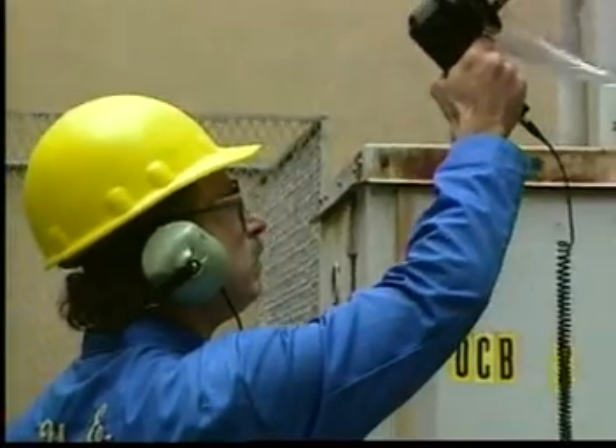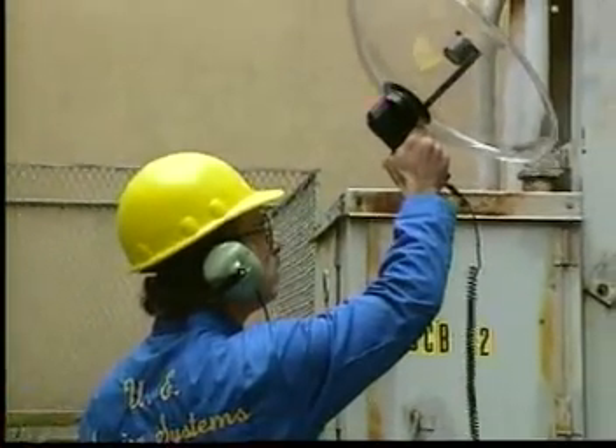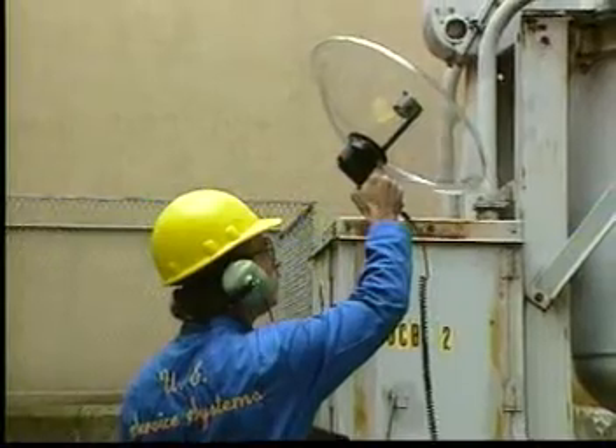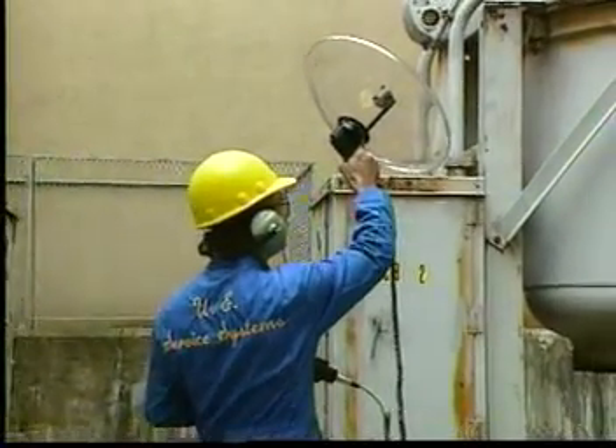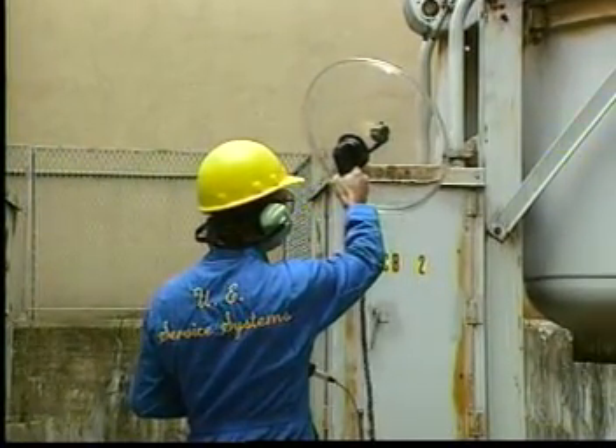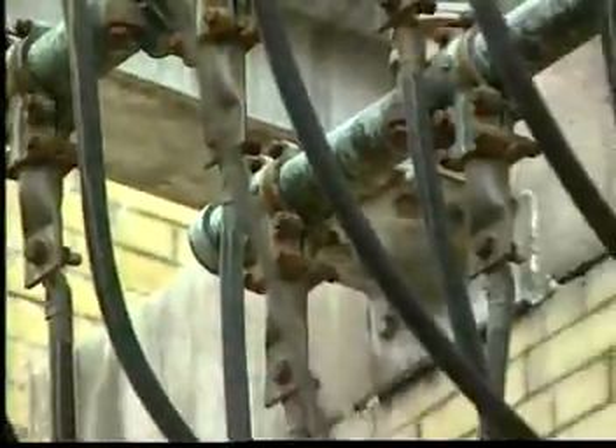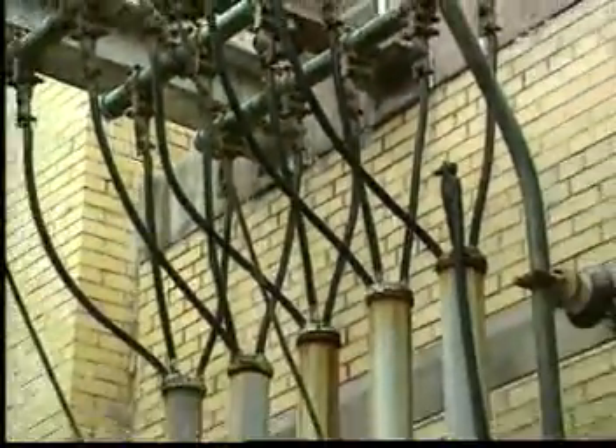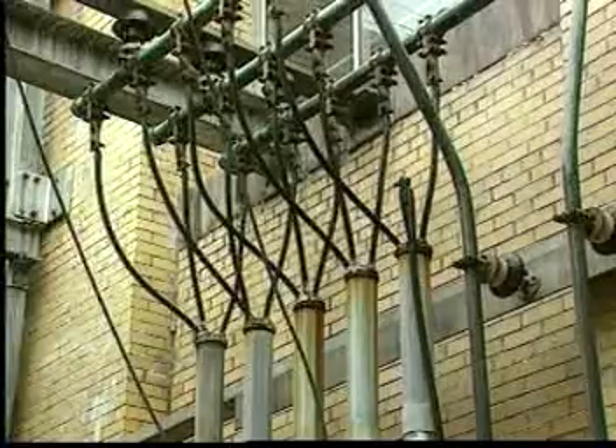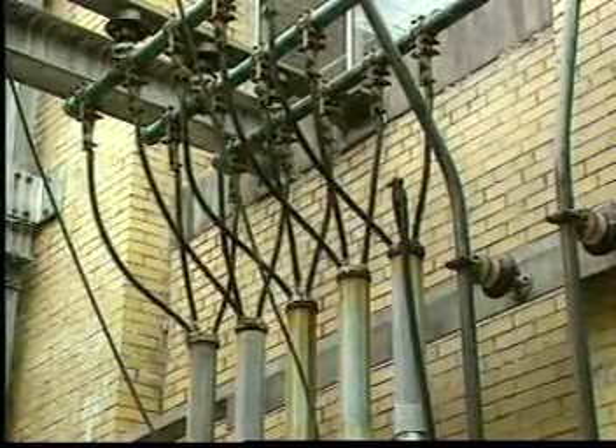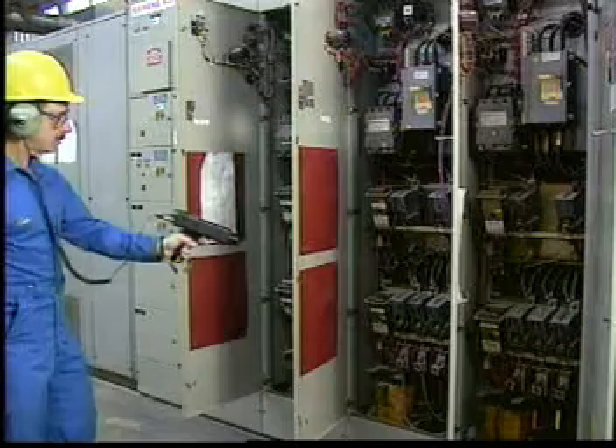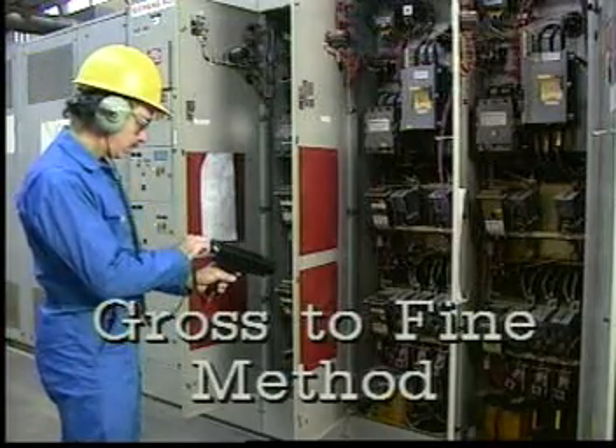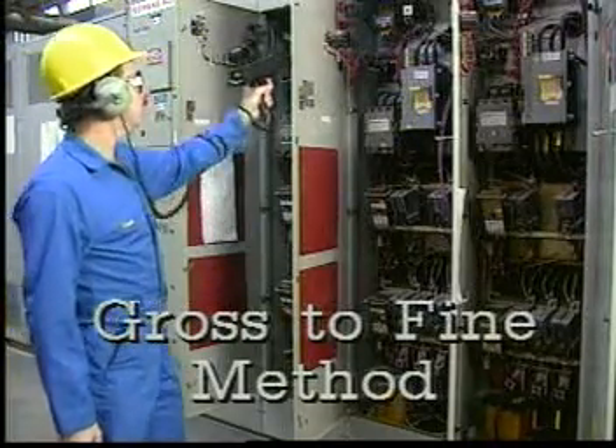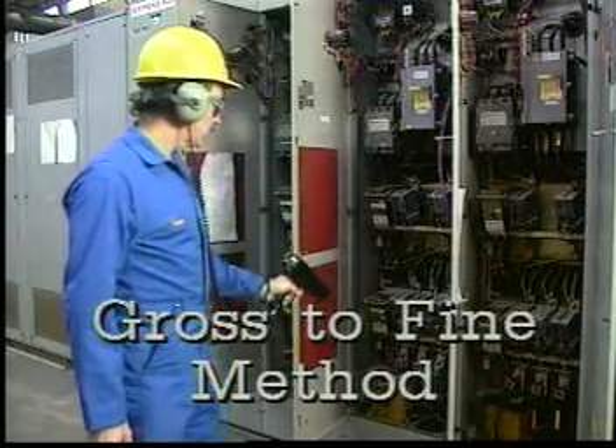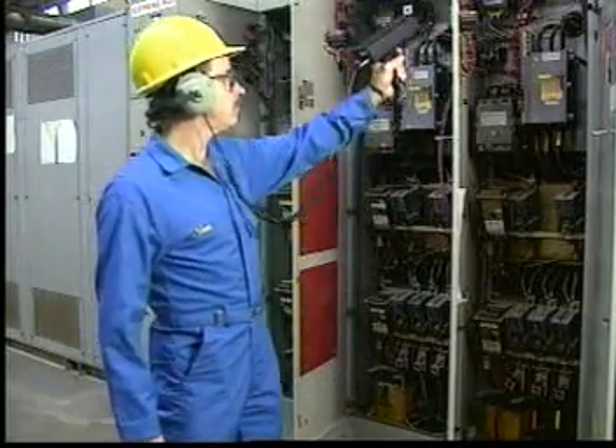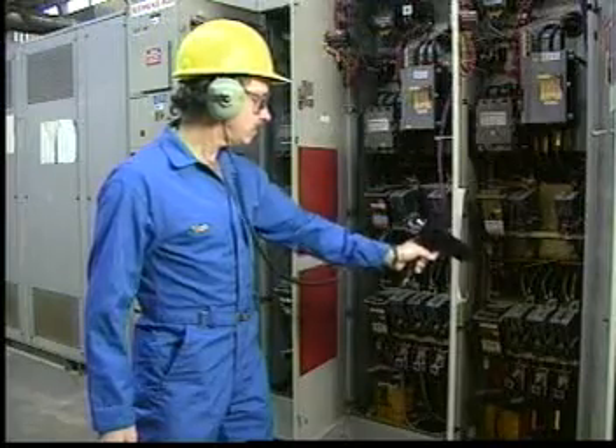The basic scanning method is used to locate the presence of electrical discharge. It can be used for virtually any area that can leak. Since anything can become damaged and therefore be a site for leakage, everything should be scanned. Here we are checking terminations, stress cones, potheads, and splices. First, using the ultraprobe scanning module, we'll follow the intensity of the signal to get closer to the site of electrical discharge. This is the first step of what we call the gross to fine method.